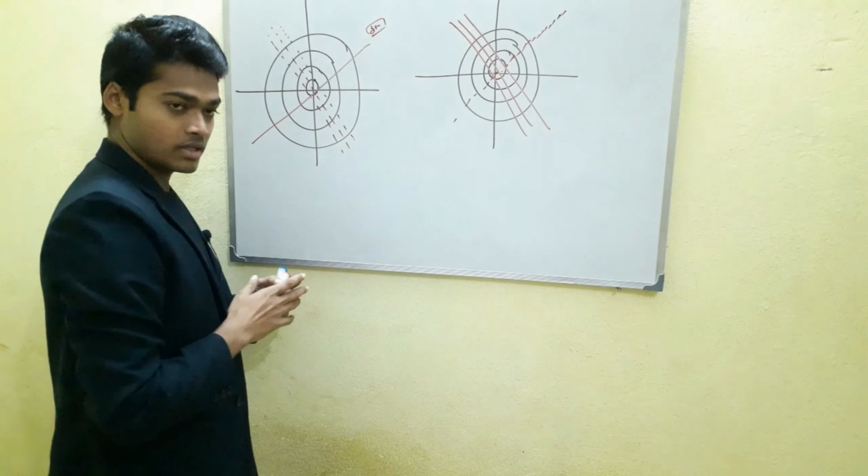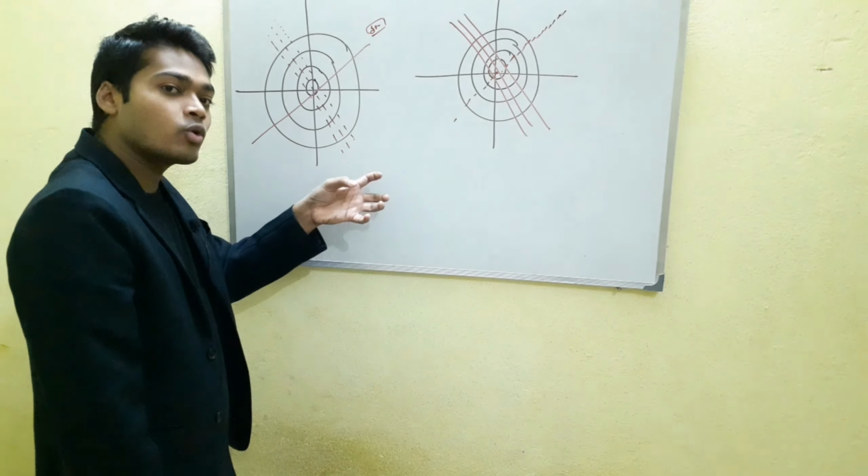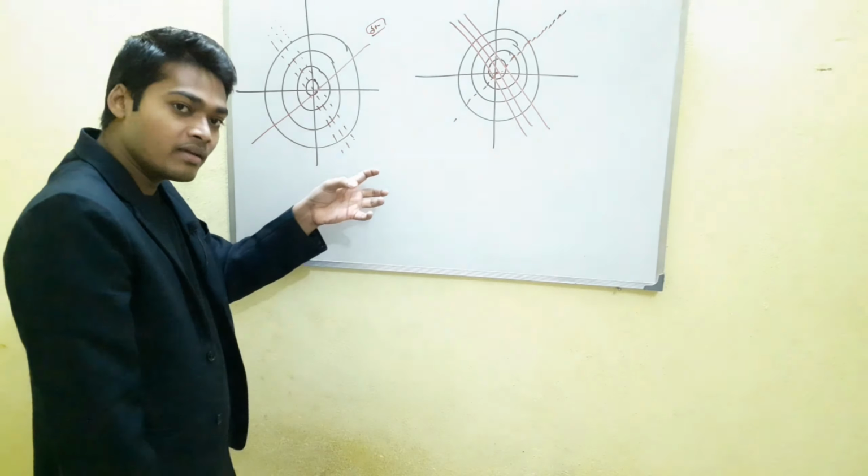Now the question is, how do we understand which one is spherical and which one is cylindrical? I already mentioned: turn the drum to the plus side, then slowly rotate in the backward direction. Where you first get the prominent single line, it means the sphere is neutralized. Then record that line. Then moving further backward into the minus side, you get the three dot line aligned. Then this is the minus value. I think up to this everybody is clear.